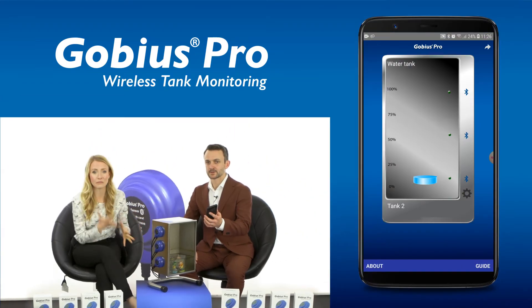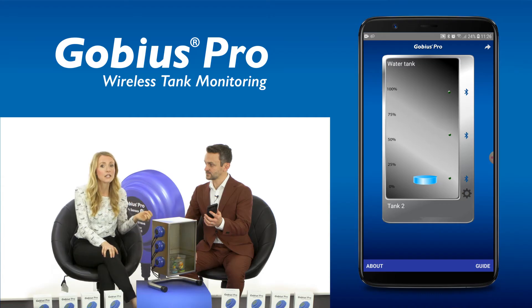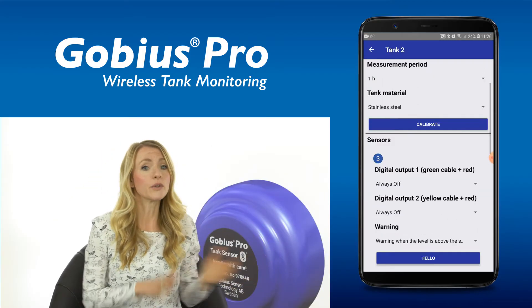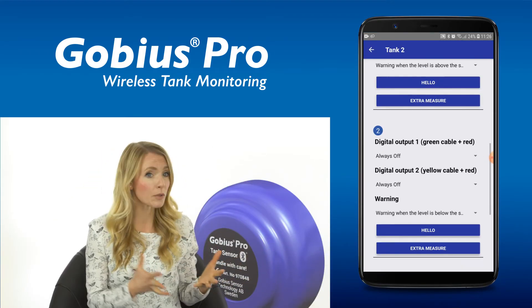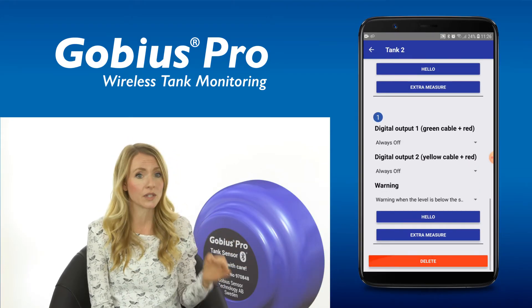That's great. Let's get the screen capture up in shot so we can see how that works. First, on multiple sensors — as they are added from the bottom of the tank upwards, each level is detected by the sensors. Here we have a tank with three sensors. The Bluetooth icons are telling us that our smartphone is connected via Bluetooth. If they are red, we are not connected. If we scroll down the screen, you see the options for setting the output warning alarm or signal for if the level is above or below the sensor.